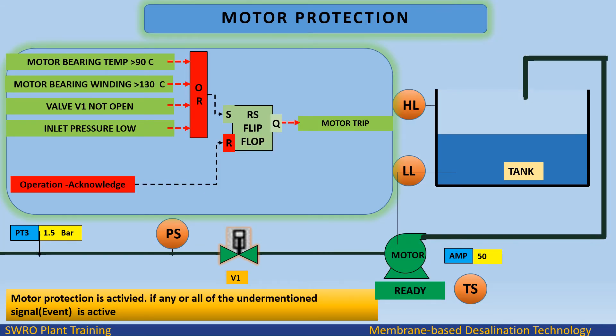Motor protection is activated if any one of the following signals is active: motor bearing temperature greater than 90 degrees, motor winding temperature greater than 130 degrees, valve V1 not open, or inlet pressure low. If any one signal is activated, it sets the RS flip-flop and the output motor trip is activated.